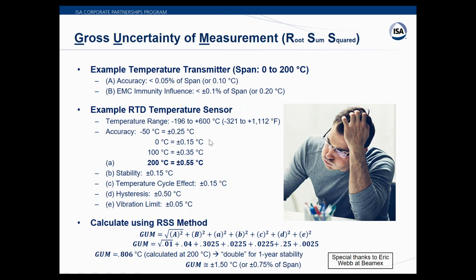Now let's look at the RTD. So this RTD has been certified or is specified to operate from nearly minus 200 to 600 degrees C, or the equivalent in Fahrenheit. And since we're talking about 200 degrees C, notice that since it's a probe, it doesn't really have a percent of span type number. It has an estimated error at freeze, you know, when it's cold, below freezing, at freezing, at boiling, and at a higher temperature. So we're going to go with what is its accuracy at 200. Since that's kind of the worst case of the numbers, and that happens to match the span here that we did. But the RTD has additional components.